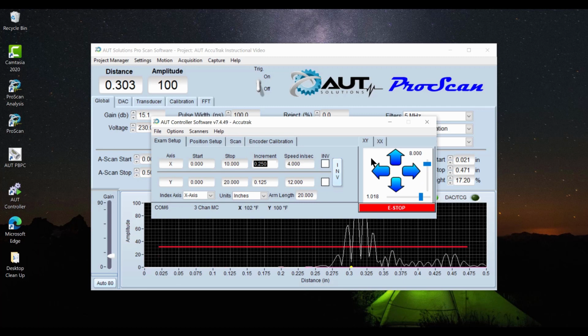If you need to move your scanner into position, you'll notice we have these arrow boxes over here. Left and right are your forward and back direction correlated to your X motor. Up and down are your Y arm. So if you need to move your Y arm over, you would simply click up. If you want to move it down, simply click down. You'll notice there are some values sitting here. You have 8 inches. This is going to be your Y arm movement speed when you hit this button. And your X movement speed here is 1 inch per second. So you can technically move that up to 2. It'll move a little bit quicker, or you can slow it down and adjust it. These values for speed control do not correlate to these. These are your inspection speeds, and these are your movement outside the inspection.